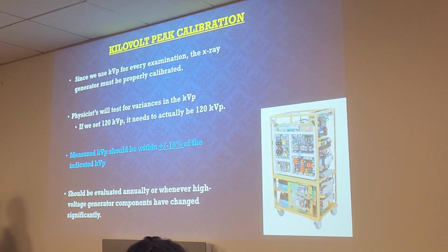Alright, so KVP calibration. So if you ever notice that big gray box or white box or whatever it is in the X-ray room, that's your generator. That's what generates your KVP. So that has to be calibrated as well every year. And when the medical physicist does their calibration, they want to make sure that it's within the range of plus or minus 10% of the indicated KVP. So if they're testing 120 KVP, they want to make sure that the range stays within that plus or minus 10% range.